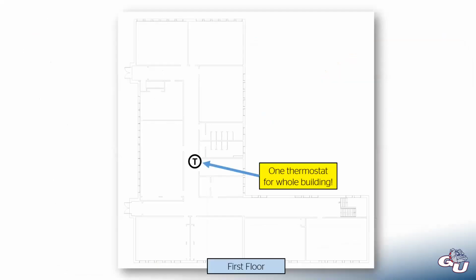It might be a little hard to see this, but this is a general floor plan of the building, so kind of an L shape here. And there were two floors to this building, but this is the main floor. So when we got there, they just had one thermostat right in the center of the building, which meant that you can see all these windows on the south side. And so as the sun goes around the south of the building and shines in all these windows, you can end up with these spaces overheating because this thermostat doesn't see that. It just knows how warm or cold it is in this hallway. So that's really not a good setup.